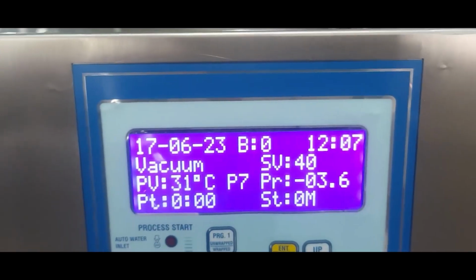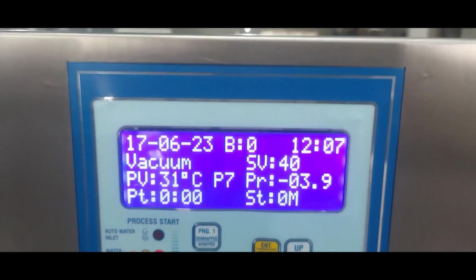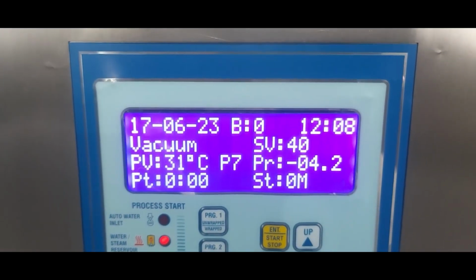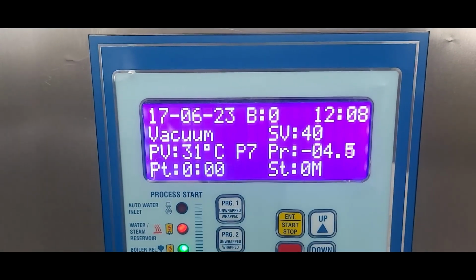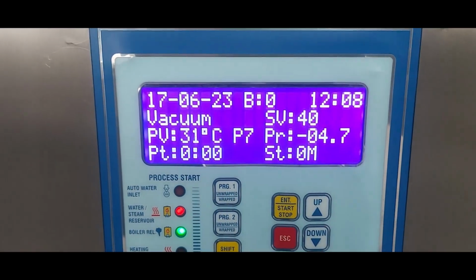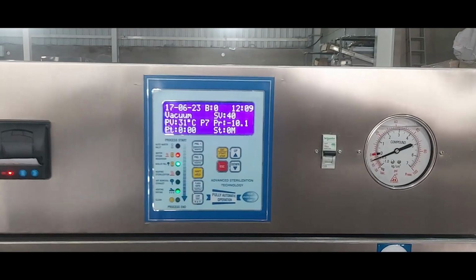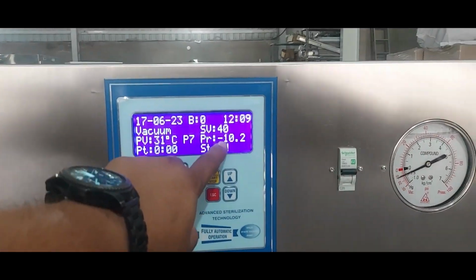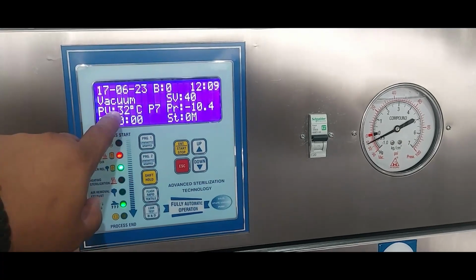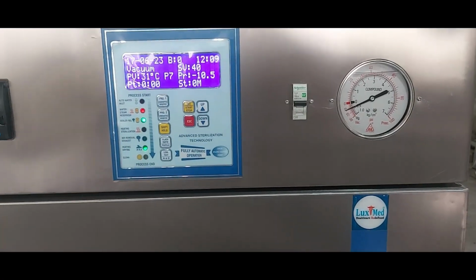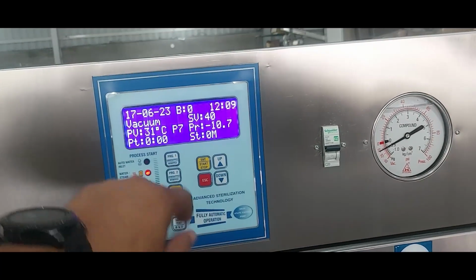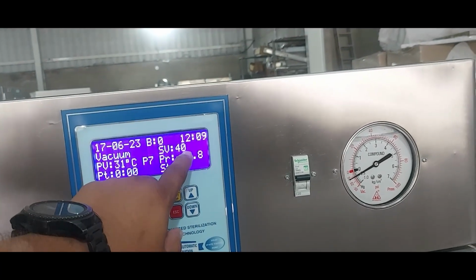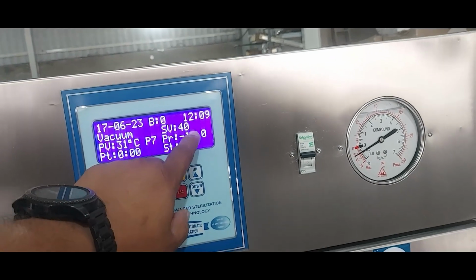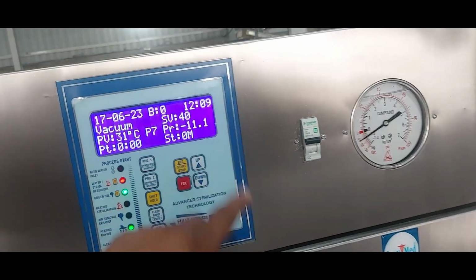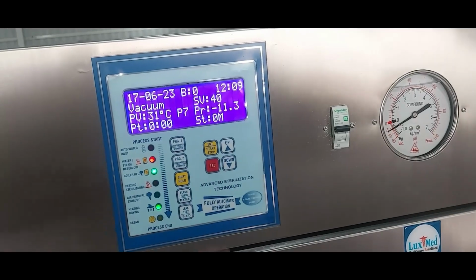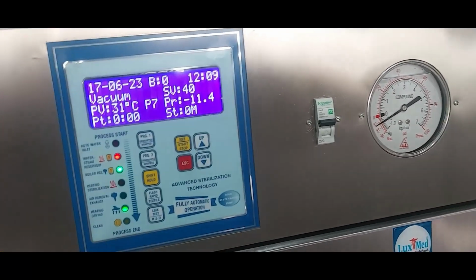The vacuum time is very fast, within 5 to 8 minutes. See, the timing is at 12:08 minutes, and the vacuum is -4 and it's going towards -25. Within 1 minute, the vacuum reached up to -10 pounds. The temperature set value is 40, because in the ETO sterilizer the temperature requirement is 35 to 55 degrees Celsius, and the pressure is minus 25. So it will reach that level and then it will start.